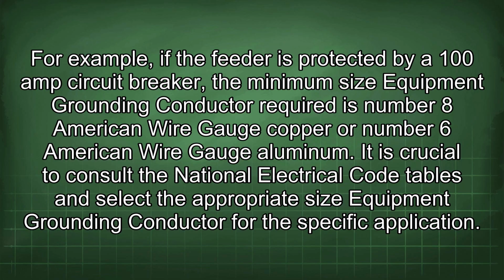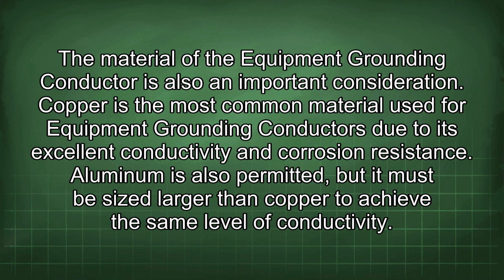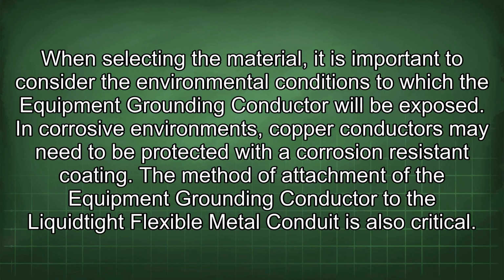It is crucial to consult the National Electrical Code tables and select the appropriate size equipment grounding conductor for the specific application. The material of the equipment grounding conductor is also an important consideration. Copper is the most common material used for equipment grounding conductors due to its excellent conductivity and corrosion resistance. Aluminum is also permitted, but it must be sized larger than copper to achieve the same level of conductivity. When selecting the material, it is important to consider the environmental conditions to which the equipment grounding conductor will be exposed. In corrosive environments, copper conductors may need to be protected with a corrosion-resistant coating.